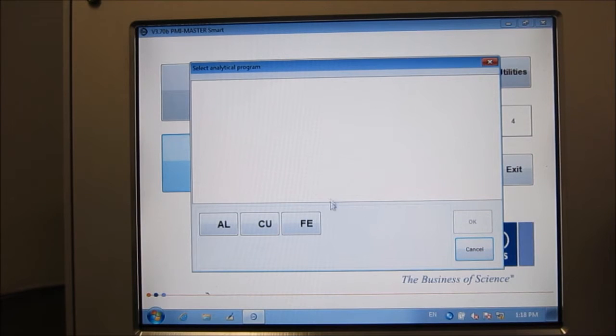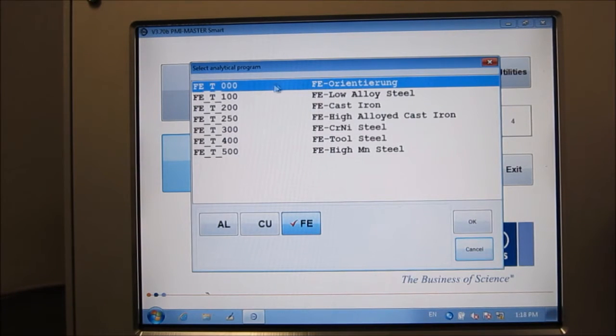Once we click on analysis, you will see a window, and this machine now has three matrices, or three metal bases, which are iron, copper and aluminium. Once you click on one of those, I will do the iron, then you'll see the sub-programs here. The first one is the universal iron program, and the rest are the sub-programs for the different steel types. Like the FE 100 is for low alloy steel, 200 for cast iron, 250 high alloy cast iron, 300 for stainless steel, 400 for tool steel, and 500 for high manganese steel. We normally choose the universal one unless we already know what type of sample we are measuring.